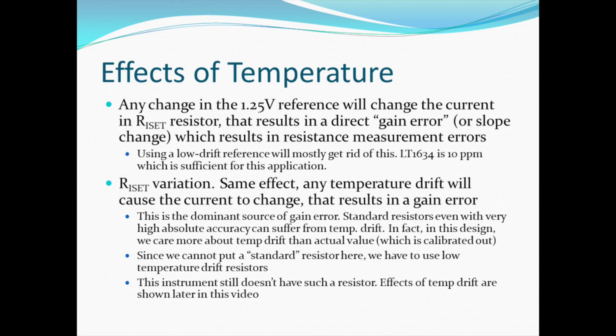So even standard resistors, which you may get with very high accuracy like 0.1%, will have temperature drift, and that's a separate effect compared to accuracy. We are not too concerned about accuracy because we do calibrate that out, but we don't want variation in that due to temperature. So even if you put a real standard resistor which has very low temperature drift, like that you use for measurements and for calibration, it's of course impossible to fit in. So we need to compromise by using a low drift tiny resistor that can fit into this box. So that's the thing we need to do as far as getting the accuracy as much as possible without affecting the performance of this instrument. So I'll probably do that in the next change. I need to just order the right device and make sure it fits into the existing area that I have on the PCB.